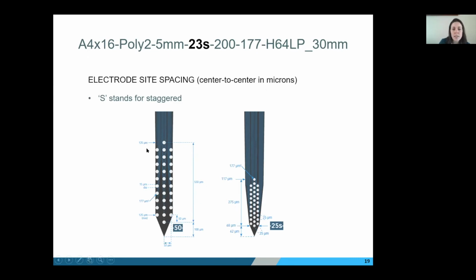When the polytrode is not staggered, the sites are in a square grid, and each side of the square is that spacing apart. So in this case, it's a 50. You can see there's a vertical spacing of 50 shown here and a horizontal spacing of 50 shown here. With the S, your sites are now in a triangular grid. They're staggered from one another. So the columns are offset, and you have the triangular grid, and you can see here that one side of the triangle is this 25, another side of the triangle is this 25. And so in the probe we're looking at here, it's 23 micron spacing.